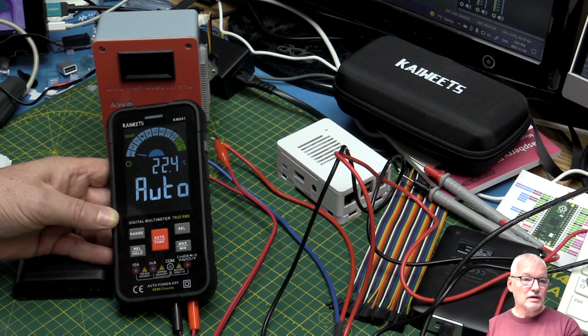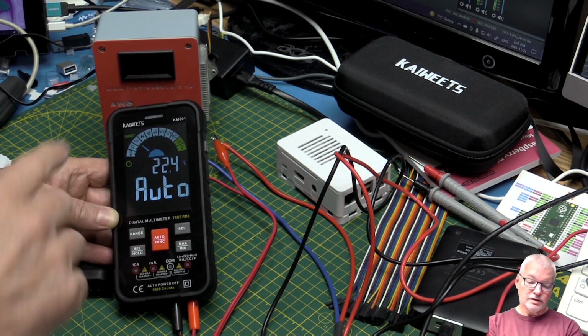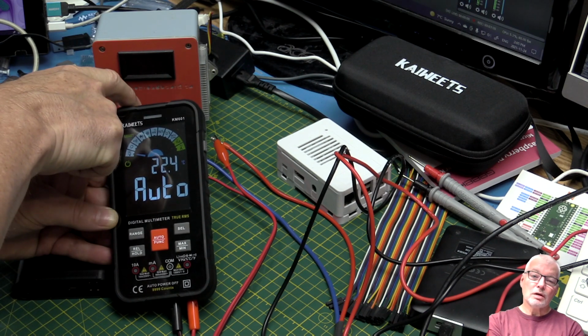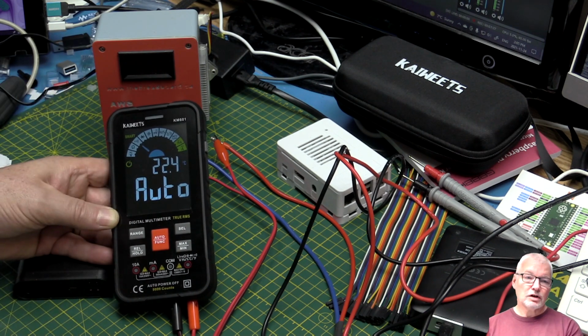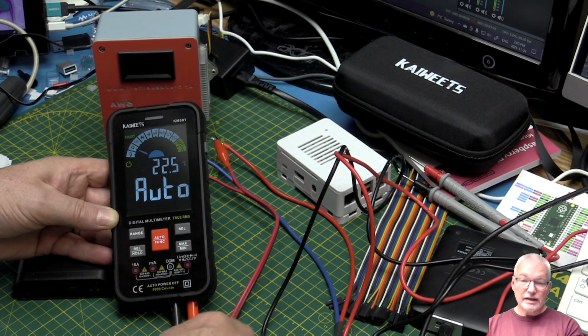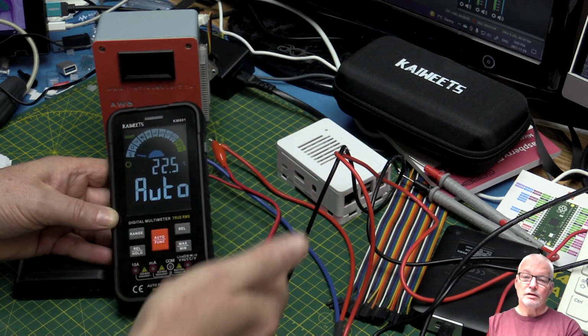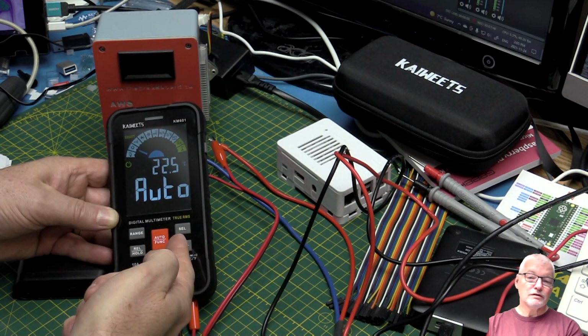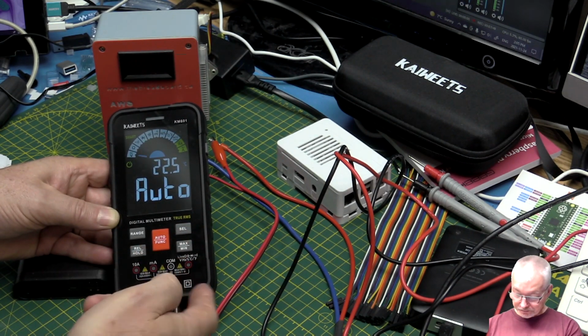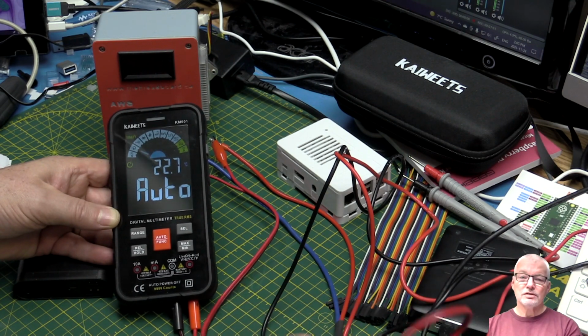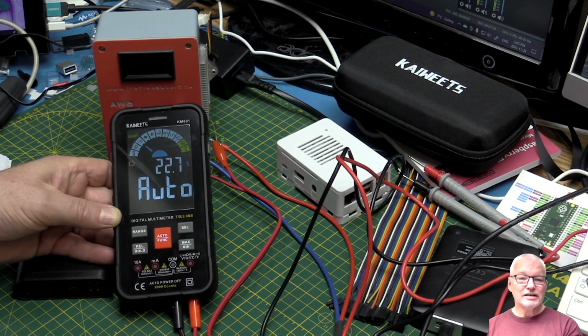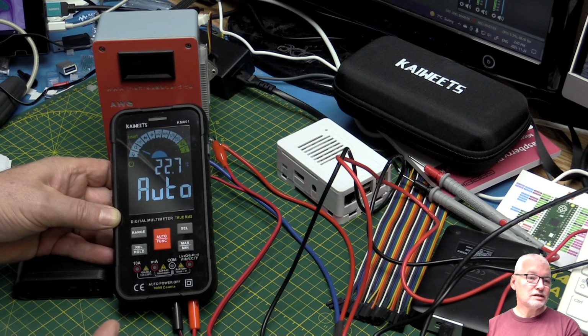Although, to be honest, there are better tools for sensing whether a main circuit is turned off than a meter. A lot of the newer ones have it, but the range here is limited. I have to be almost on top of it to sense it. So if you're trying to see if a socket is still live, it's not going to do that for you unless you plug the lead in, in which case you're bringing 120 or 240, 50 volts right up to the meter. And I would be reluctant to use them on that. But I say that for all the meters in the $50, $60 range.